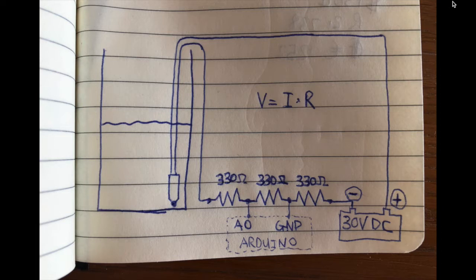I've got a very basic circuit diagram here: a 30 volt DC power supply, 3 resistors, and a water level sensor. This dot is the actual sensor. It outputs a very small signal, which we need to convert, and that's what this block represents: the transmitter. The transmitter converts the signal from the sensor to a current of between 4 and 20 milliamps. A transducer, by contrast, converts the signal to a voltage instead of a current, but we're using a transmitter, so we get a current output. The Arduino is what I'm using to make the measurement, and it can only measure voltage, between 0 and 5 volts, which is why I've chosen a 330 ohm resistor, to make full use of the Arduino's range.